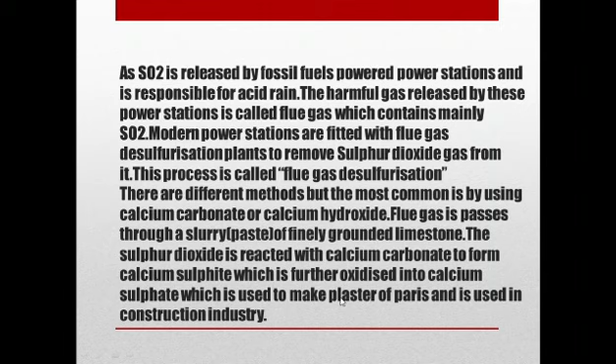The flue gas desulfurization that we are studying today, this process is called wet flue gas desulfurization. This is wet flue gas desulfurization because in this process, a slurry of calcium carbonate is used and that is sprayed on the flue gas. Now, the process is based on a slurry of slaked lime, like calcium hydroxide. The paste of calcium hydroxide is sprayed and that reacts with sulfur dioxide and forms calcium sulfite and water. Because you know that the oxides of non-metals are acids and this is the hydroxide base. So when acid and base are reacted, salt and water is formed.